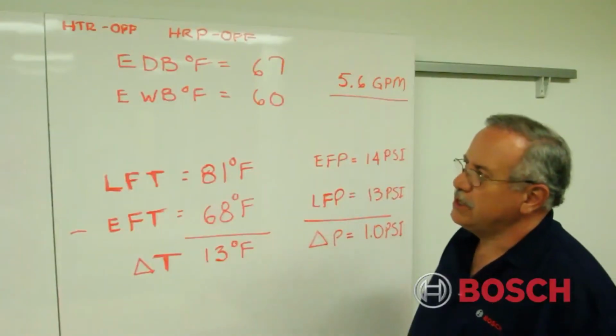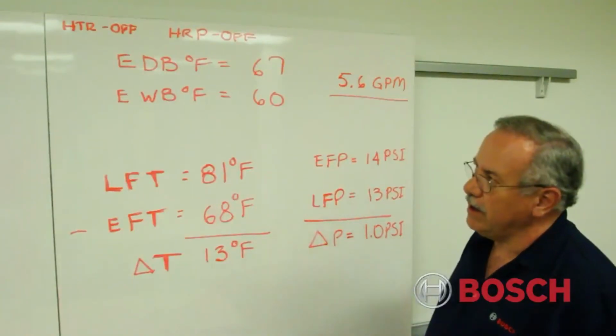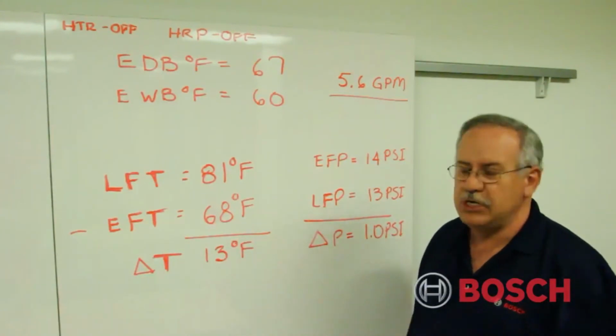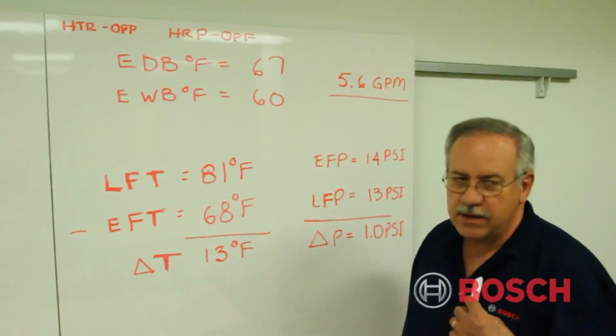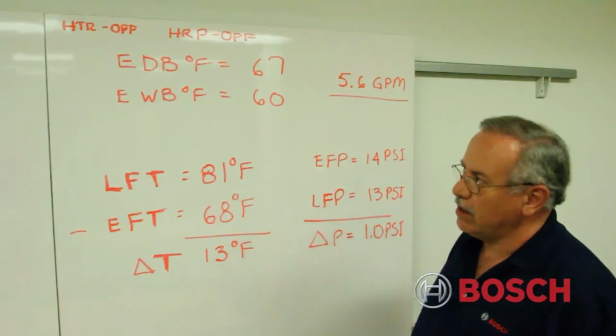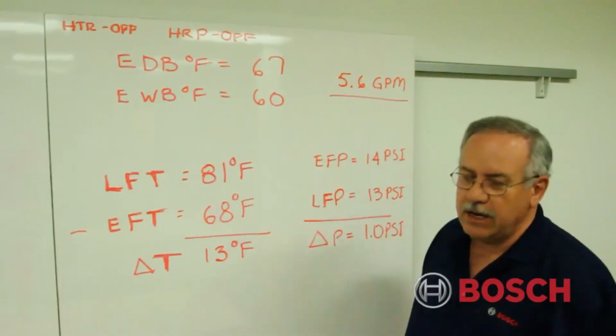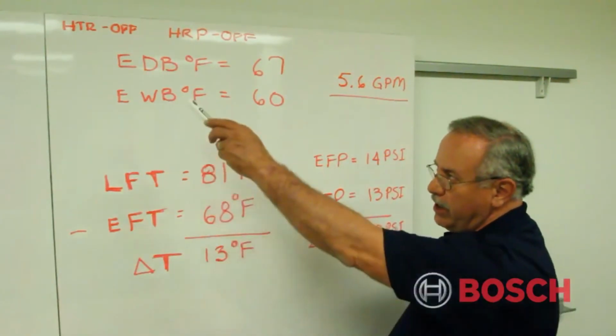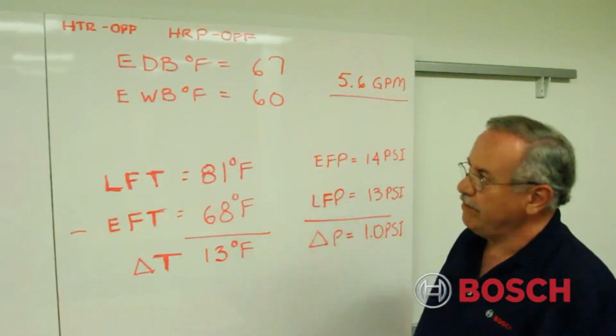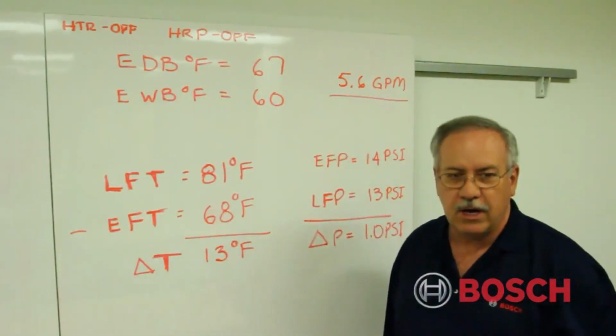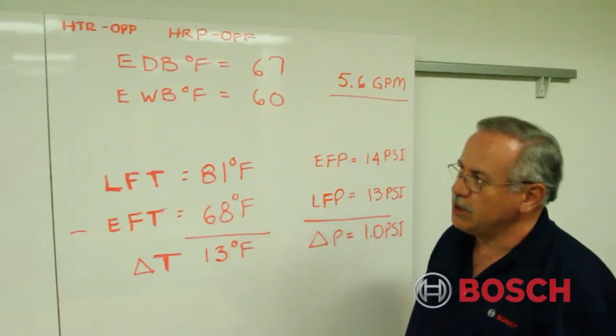Okay, so what you've just seen is my counterpart Mark gathering data from the live machine. We're talking about a TAO25. We are operating it in cooling, so we're calculating heat of rejection. We want to make sure that any electric heaters are off, as well as any heat recovery package, commonly referred to as the superheater.